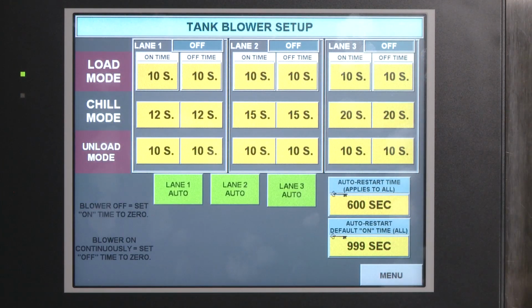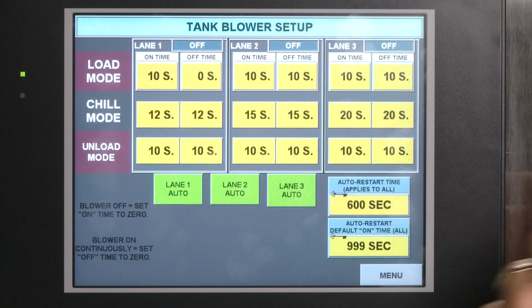The blower has two modes of operation: timed mode and continuous mode. The continuous mode allows the blowers to run continuously when a value of 0 is entered for the off time. It will shut off if a value of 0 is entered for the on time. When the lane mode is off and the refrigeration is on, the blower will run continuously.